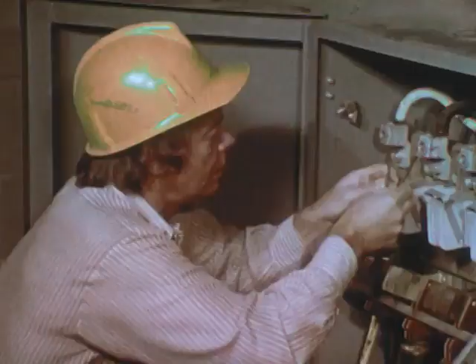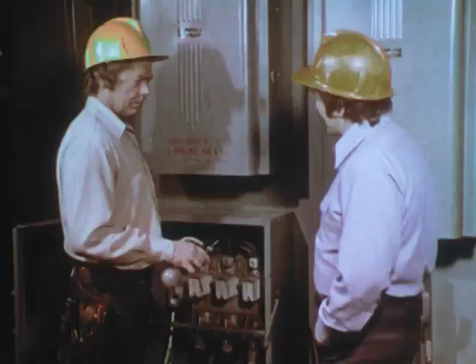Hey, wait a minute. Just what do you think you're doing with that pigtail? My job, any objections? That's a 600-volt three-phase circuit. You stick a 110-volt tester in there and that bulb will explode faster than you can blink. Use a voltmeter or a ground fault detector to check the circuit.